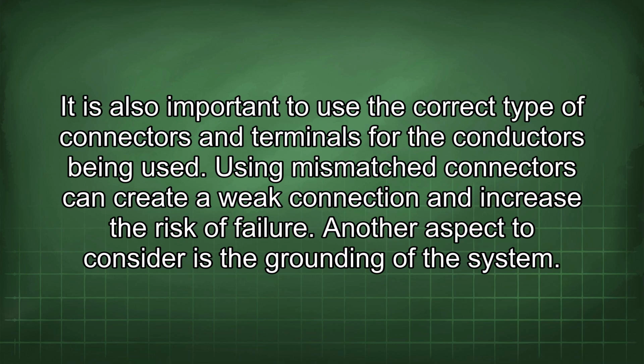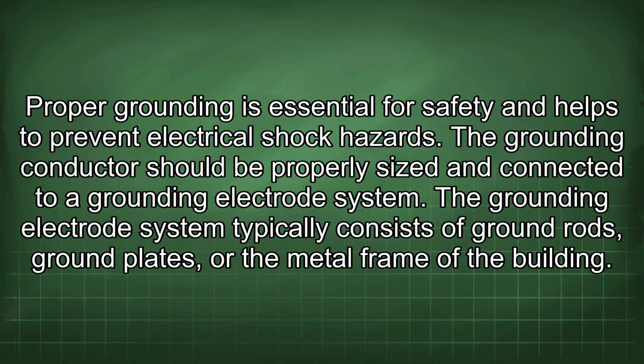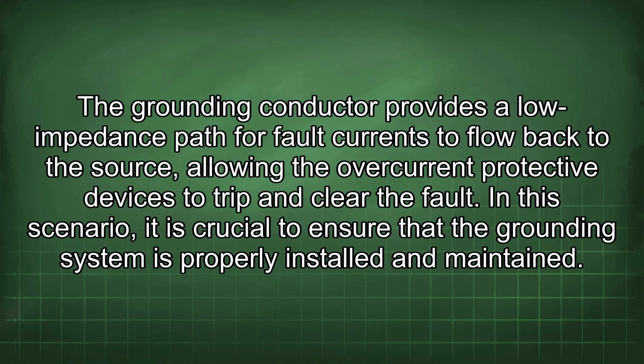Another aspect to consider is the grounding of the system. Proper grounding is essential for safety and helps to prevent electrical shock hazards. The grounding conductor should be properly sized and connected to a grounding electrode system. The grounding electrode system typically consists of ground rods, ground plates, or the metal frame of the building. The grounding conductor provides a low impedance path for fault currents to flow back to the source, allowing the overcurrent protective devices to trip and clear the fault.